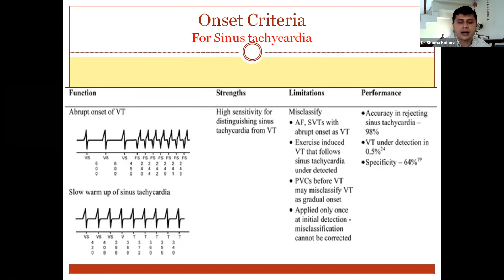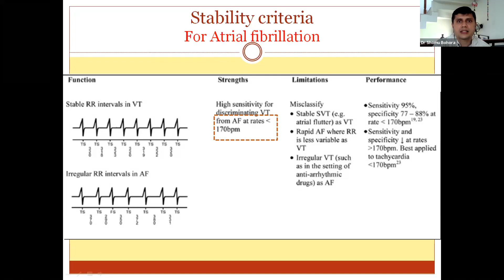So more RR variation. However, it can occur in ventricular tachycardia in the initial and the later stage also. However, most important is that a persistent RR variability suggests atrial fibrillation, and that gives a clue. There is a programmable rate at which the device will say, after this, I will not consider it to be an SVT at all. So they generally consider 200 and above because SVT should not conduct more than a 200 rate. That's where the AV node comes into the picture. So if it is more than a 200 or 220 rate, it will say, no, it's always a VT unless proved otherwise, and it will shock.